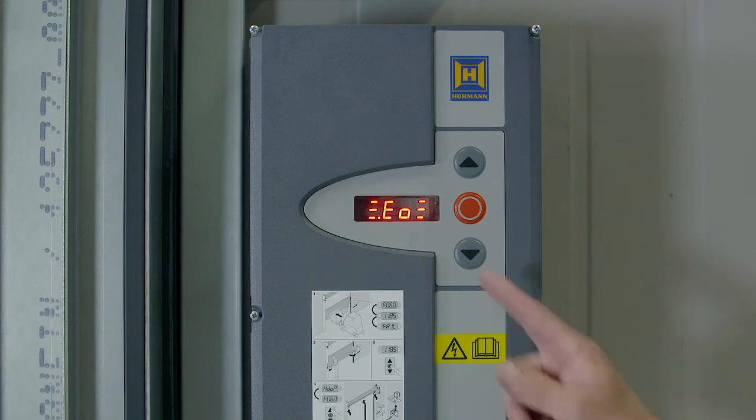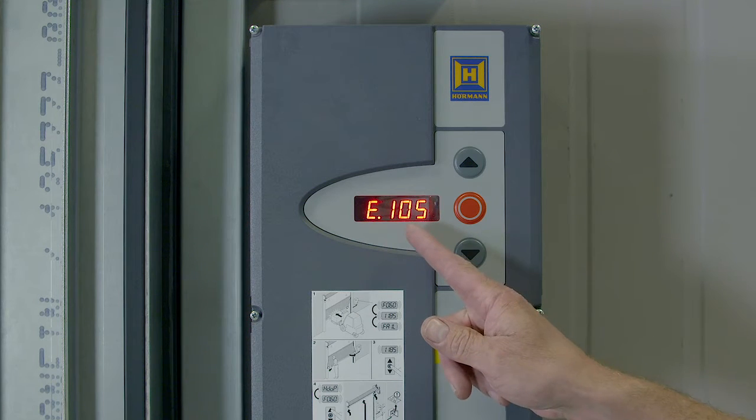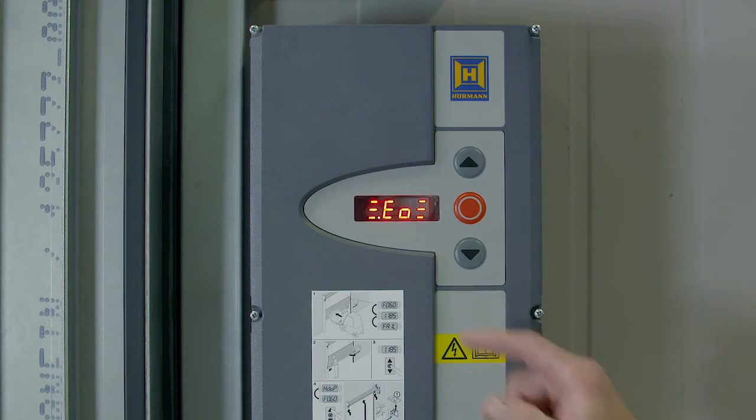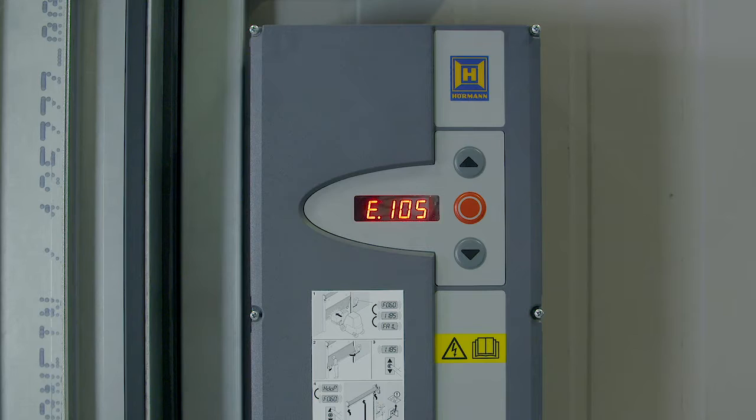Before we start, please ensure that the installation of your door is mechanically and electrically complete. The input E105 is displayed when the light curtain or grille is activated, but it can also display if there is a fault with the light curtain.